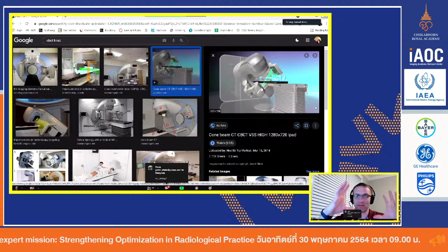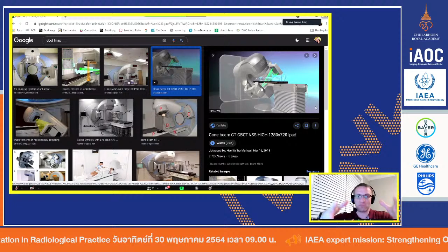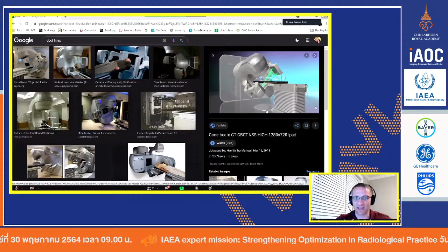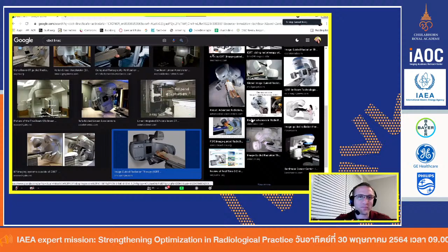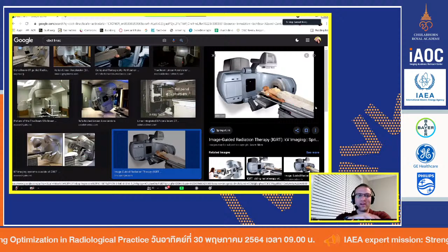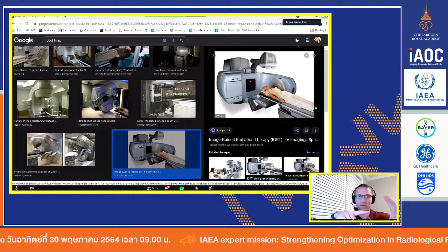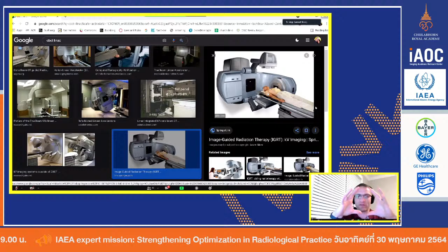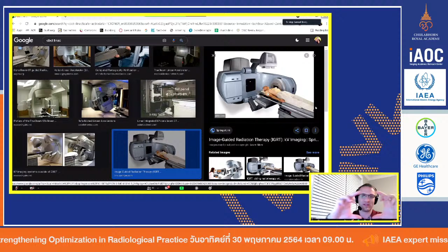And because of the trajectory and the limitations of where they can actually image in the body, if you have a large body on the table, well, that's not exactly a large person, but if you have a large body on the table, you actually have to shift the patient. In a normal CT scanner, the field of view is large enough, 50 centimeters. We can do one full spin and get a full 50 centimeter field of view. In these, the field of view is smaller. So if you're doing, say, liver imaging, you'll center the rotation over the liver. So the patient is shifted and you spin around. You don't get the whole abdomen, only the liver. But because it's offset, you also get a lot of artifacting.